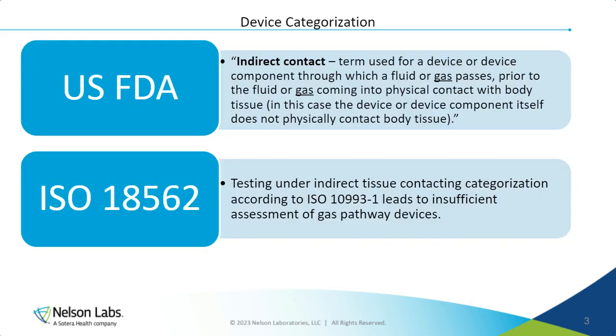While the categorization is something that most of us are familiar with, it won't hurt to briefly touch on it, so we're all on the same page. The term indirect contact is used for a device or the device components in which a fluid or gas pass through before they come into physical contact with the body or body tissues. We can usually look at this as the device component does not physically contact the body or tissue. Furthermore, according to ISO 10993-1, this indirect tissue contacting will lead to insufficient assessment and testing of these gas pathway devices. This is really where ISO 18562 becomes the star player.